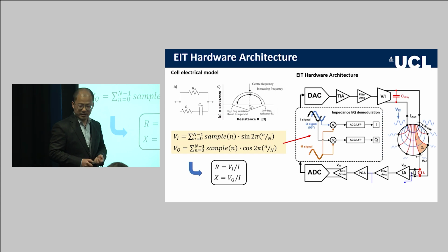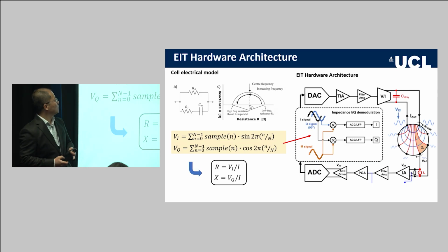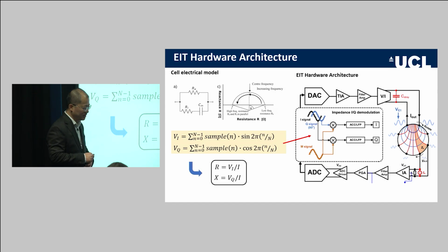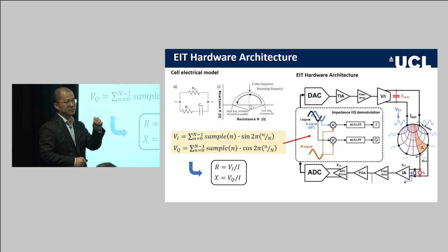And to reduce the energy demand, what we need to do is to look at the principle of impedance measurement. So this is a very simple principle. This is an electrical model of the human cell. As you can see, there is resistive element, there is capacitive element. So if we inject a sinusoidal wave and measure the response, we can detect the change in the magnitude and the phase so that we can work out the resistive element and the reactive element.